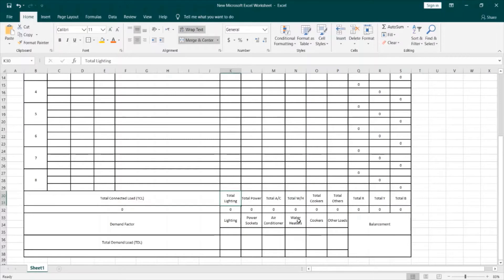The demand factor is always between 0 and less than or equal to 1. On the other hand, diversity factor is the ratio of the sum of individual maximum demands of a system to the maximum demand of the whole system. In our case, we separated the loads according to their purposes. For lighting loads, for example, throughout the day we will not be turning them on for 24 hours — the maximum demand will be at evening time. Also, depending on the nature of the project, whether it's commercial, industrial, or residential, we can study and envisage the demand factor.